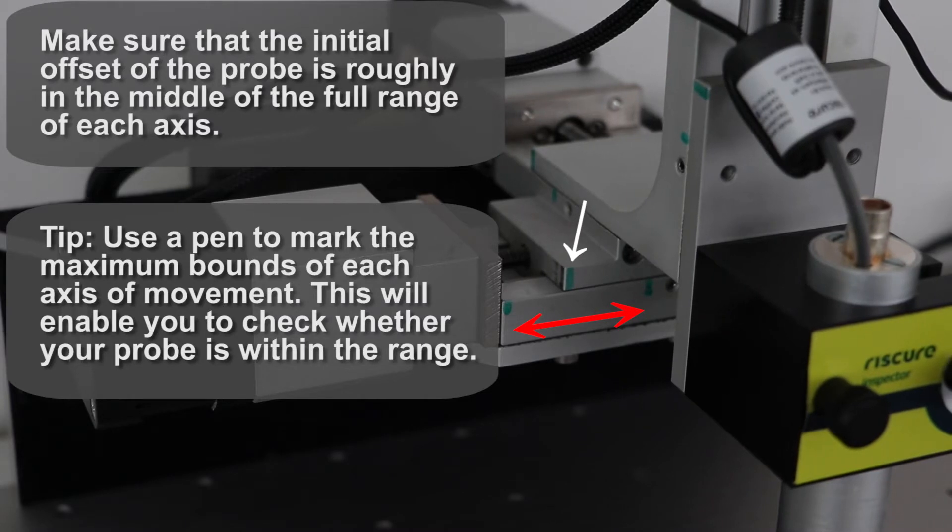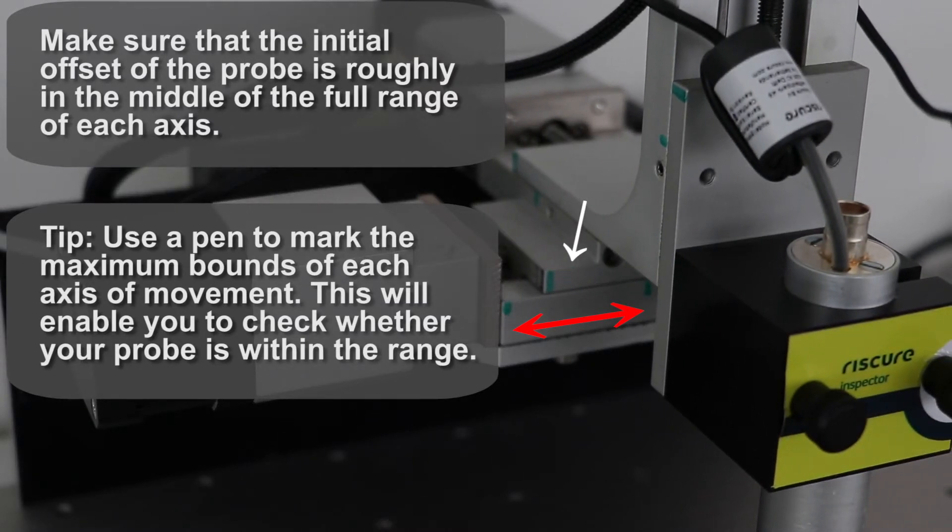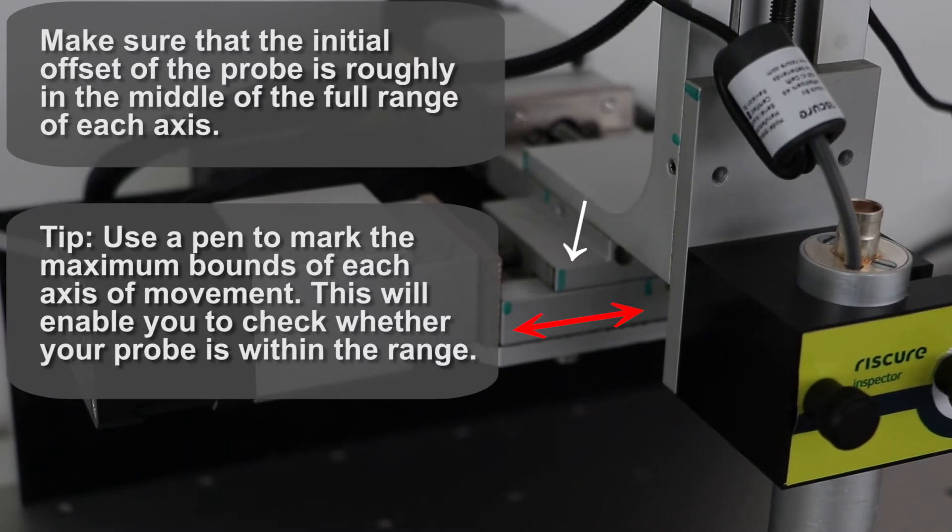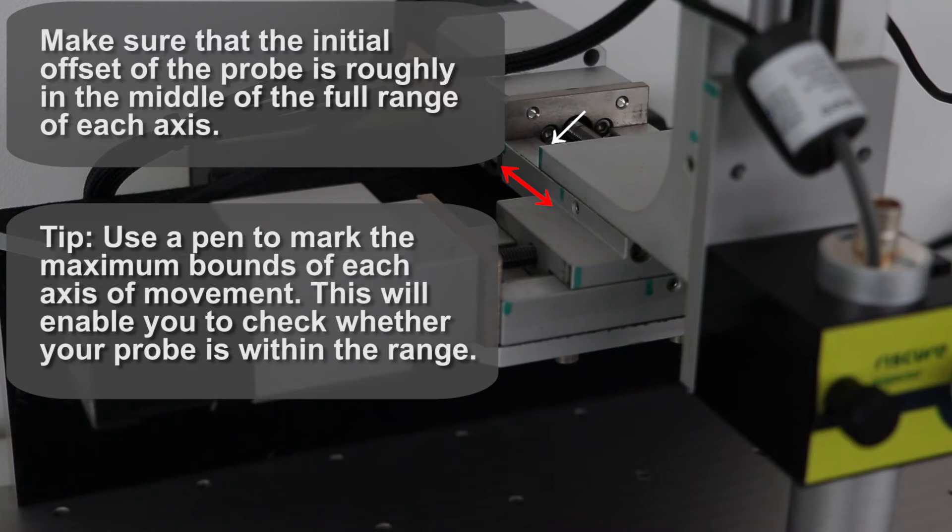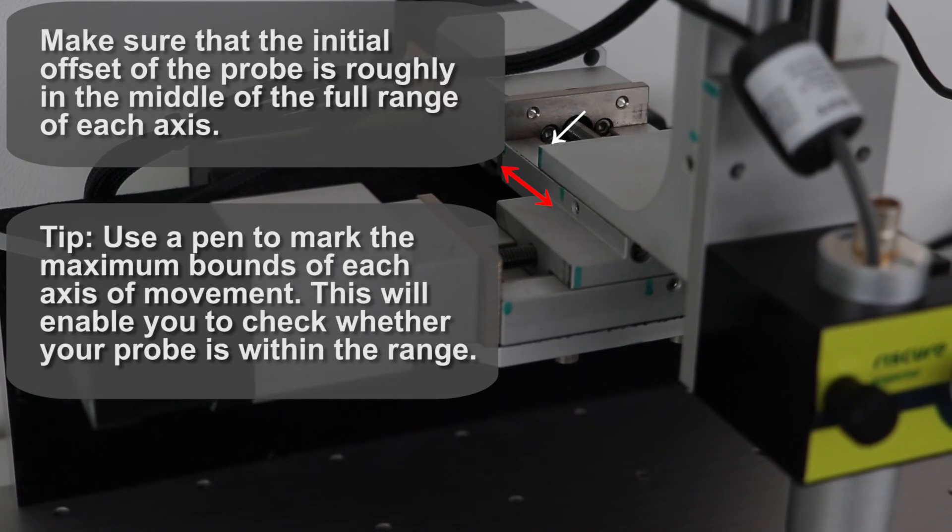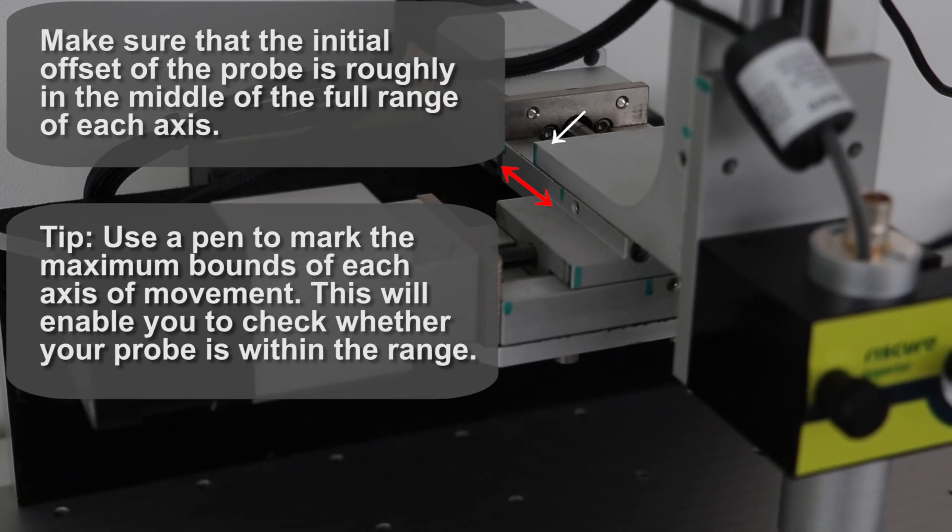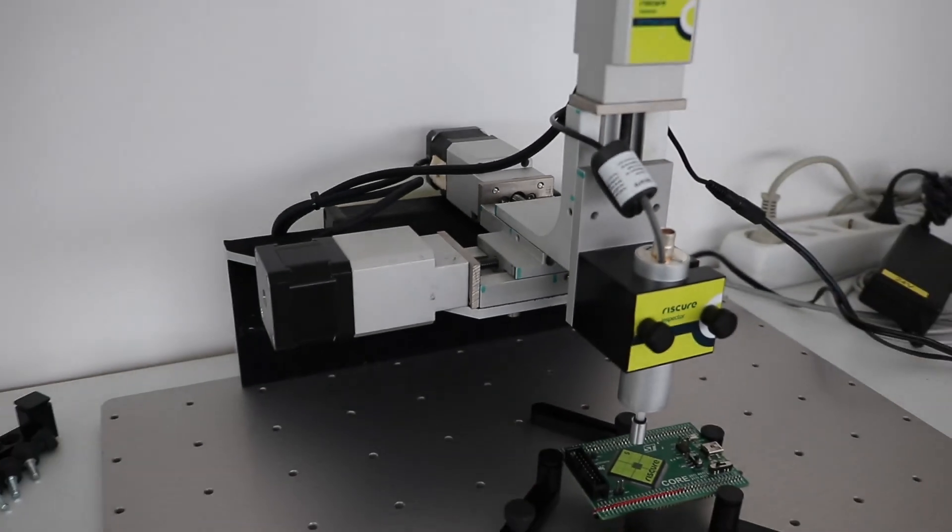Make sure from the very beginning that the initial offset of the probe is roughly in the middle of its full range of each axis. A nice tip is to mark the points that the probe can reach at each axis with a marker. In that way, you'll always be aware of whether you are inside the range of the station. Follow these tips and good luck!